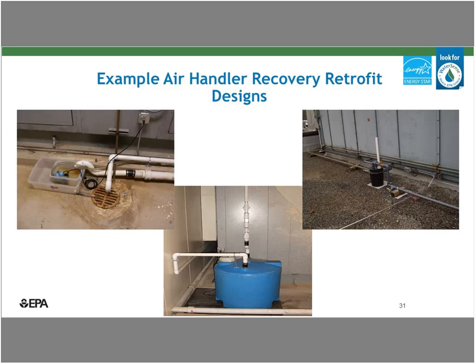The biggest challenge with this type of reuse project is just the plumbing that's required to get the water from the air handlers to the cooling tower. However, if your pipe runs aren't too long or complicated, or if your air handlers are nearby the cooling tower basins, they can be very, very cost-effective projects. These are just some examples of some, albeit rudimentary, projects that have been incorporated in some facilities that I'm familiar with. So they really don't need to be complex. It can be a little bit of pipe, some containers to collect the water, and a submersible pump to get it to the cooling tower basin.